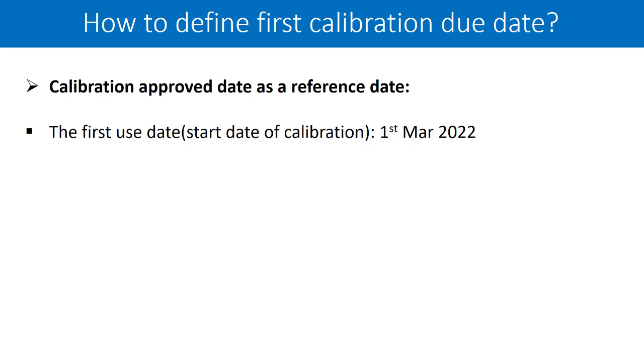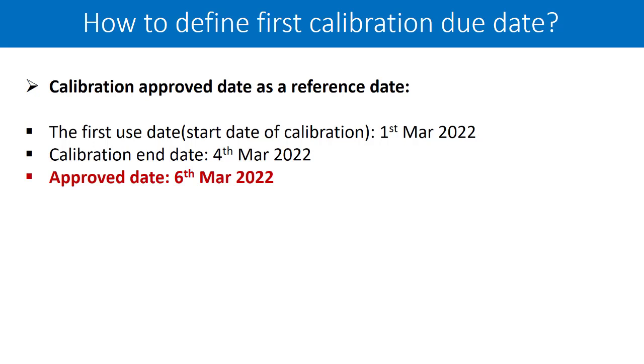I am talking about the effectiveness of your SOP, not the qualification, because the qualification comes before the implementation of your SOP or the calibration methodologies. So your first use is actually your calibration start date. On this date you used the instrument for the very first time, and that happened to be 1st March 2022 in this example. The calibration end date is 4th March 2022 and the approval date is 6th March 2022. Based on the approval date as the reference date, the calibration due date should be 6th September 2022.